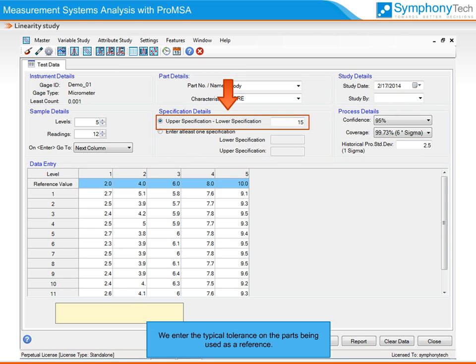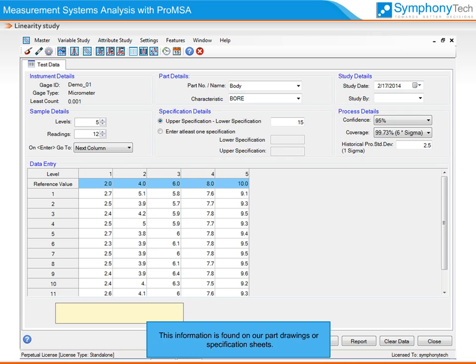We enter the typical tolerance on the parts being used as reference. Once again, we may want to use the tolerance on the most critical parameter the instrument measures. This information is found on our part drawings or specification sheets.